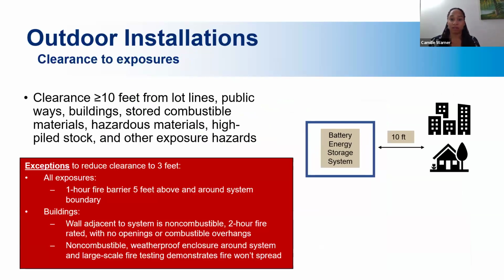For outdoor installations, the fire code requires 10 feet of clearance around the footprint of the system. This distance can be used as a fire barrier. It can be reduced by large-scale fire testing. So if you do 9540A and that test says you can put it at 9 feet, then that's something the developer can consider if the test verifies that that's the case. The fire barrier should be at least 1-hour fire rated.